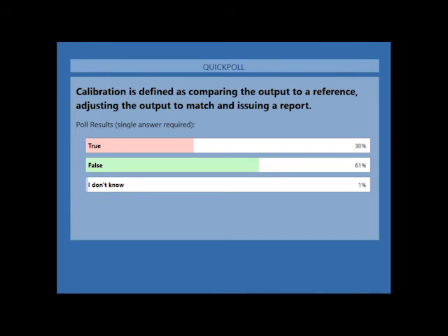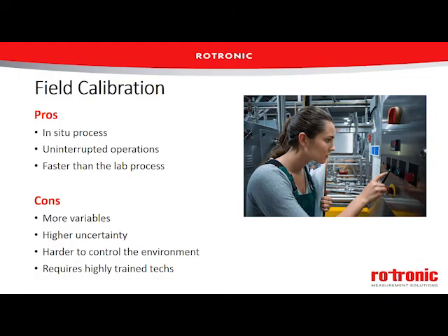And the answer is false. Remember, we just went over calibration is just comparing the output to a reference and issuing a report. And again, I know it's a little bit ambiguous because a service called calibration maybe could be argued is different than the term calibration. But we can have that debate some other day, right, Michael? That's right.